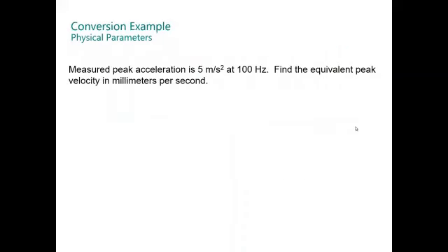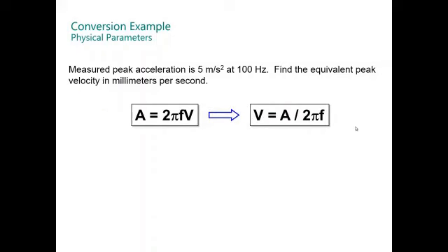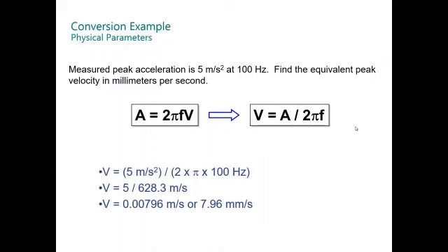One example: you have a measurement of 5 meters per second squared at 100 hertz. Find the equivalent peak velocity in millimeters per second. The acceleration is 2πf times velocity. Now the velocity is acceleration divided by 2πf. The velocity is 5 meters per second squared divided by 2π times 100 hertz, or 0.00796 meters per second or 7.96 millimeters per second.